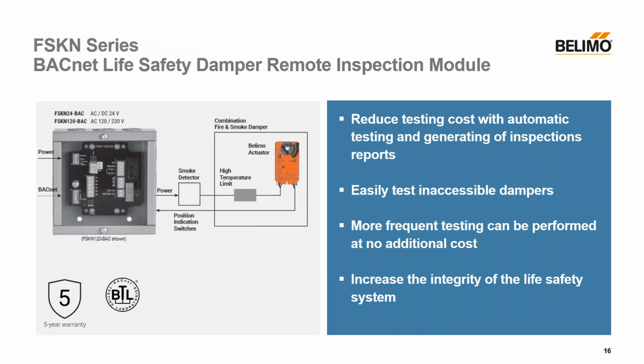We also have an FSKN, which is a BACnet life safety damper remote inspection module. This is due for Q3 release, and it allows testing of actuated life safety dampers without costly visual inspections. The module initiates damper cycling and verifies damper position to ensure proper operation in emergency situations. It connects seamlessly to fire alarm panels or building automation systems using BACnet or Modbus communication protocols.